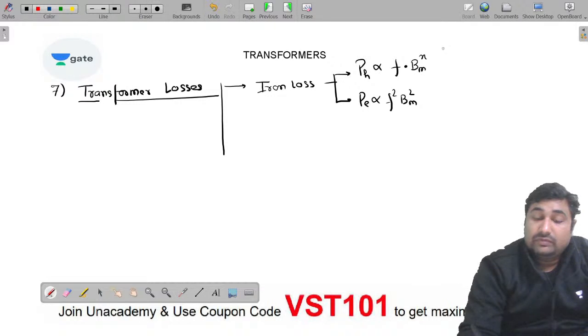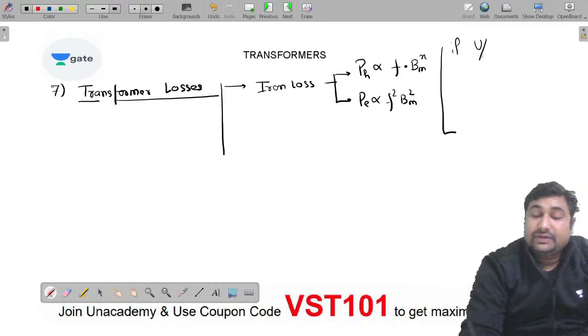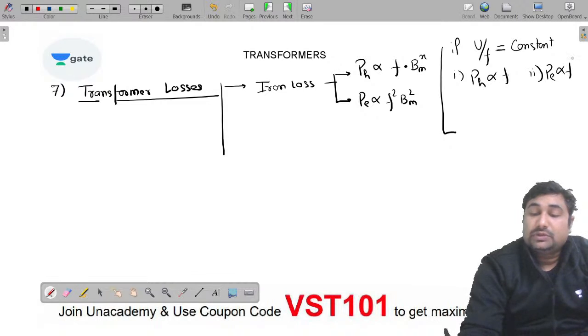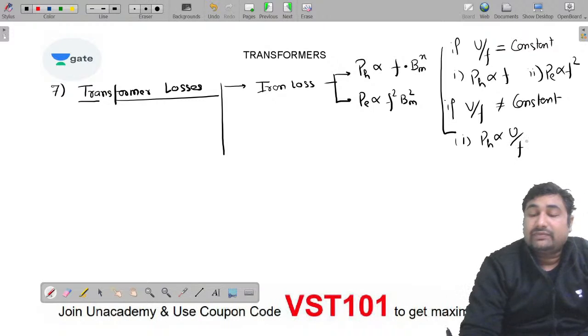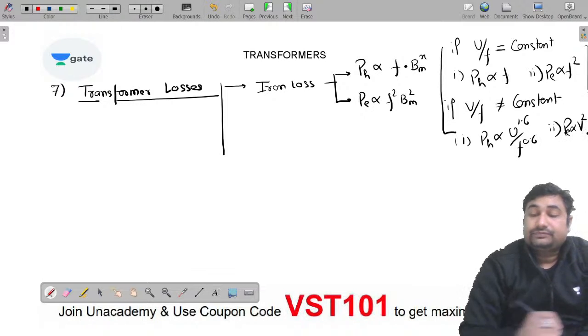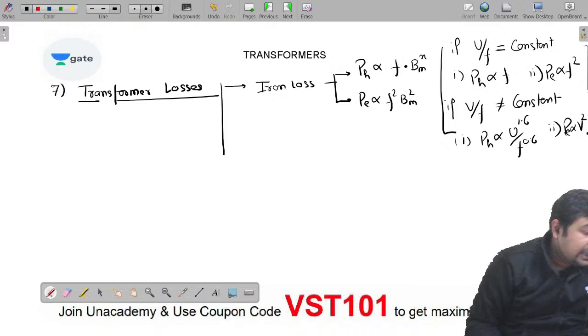ठीक है sir. Always you have to remember one more thing, that is V by F. So I am writing here, please see. If V by F ratio is constant, then always remember hysteresis loss is proportional to frequency, while eddy current loss is proportional to square of the frequency. In case if V by F ratio is not constant, then sir, first is your hysteresis loss is proportional to V to the power 1.6 by F to the power 0.6, and eddy current loss is proportional to V square. Okay, बोलिएगा क्या मेरी बात समझ में आई? Are you getting this thing?